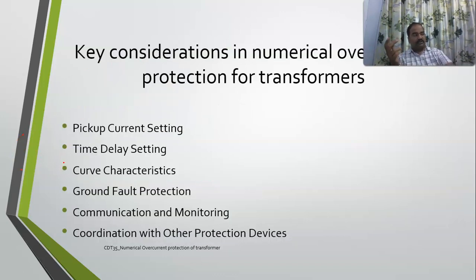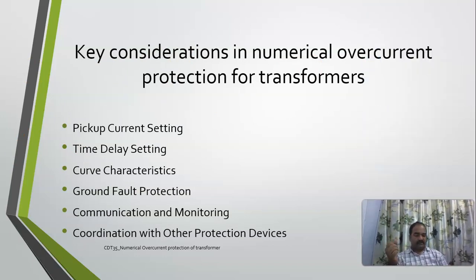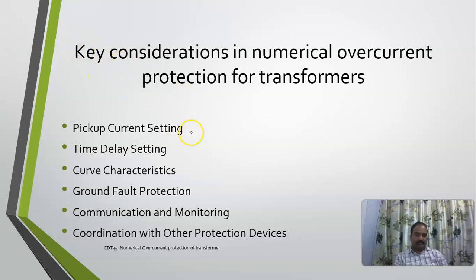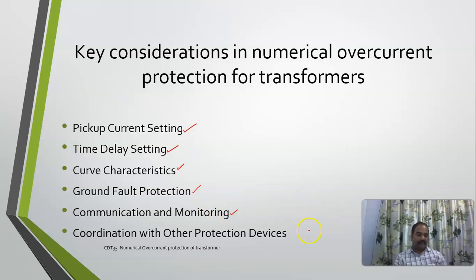Whenever we talk about overcurrent protection of transformers, there are some key things to keep in mind before implementing a numerical overcurrent design. The key considerations are: pickup current setting, time delay setting, the characteristics of the curve you want to implement, whether to include ground fault protection, and whether you are communicating and coordinating well with other protection devices.